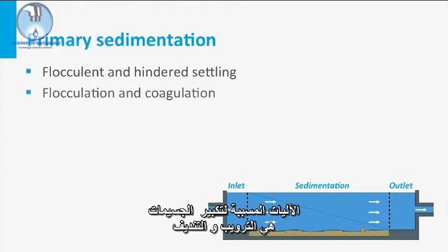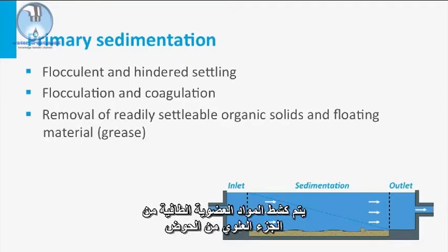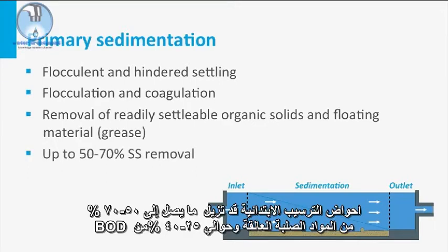The occurring mechanisms of particle enlargement are flocculation and coagulation. In the primary clarifier, the settleable organic solids are removed via the bottom, whereas the floating organic matter is skimmed from the top part of the tank. A primary clarifier may remove up to 50-70% of the suspended solids and about 25-40% of the BOD.